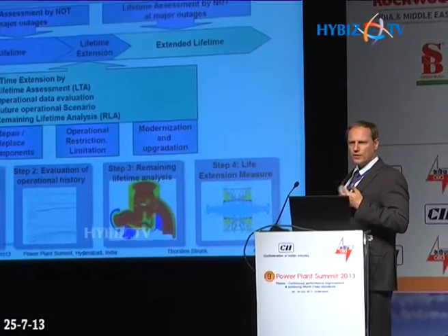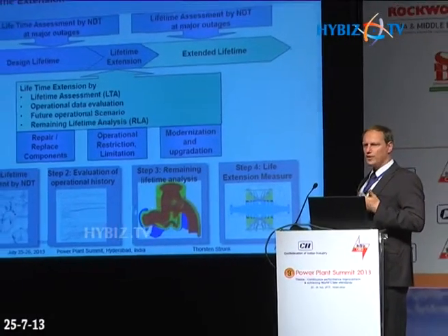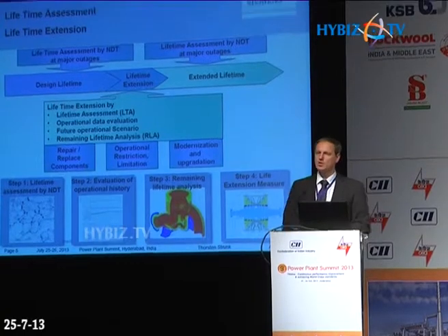And then you can do the remaining lifetime analysis, which brings you the result on which basis you can make a sound decision of what lifetime extension measures you would need to take in order to get the best bang for the buck. We used to say the most return of investment. This could mean that you say, I'm just restricting my operational mode, and maybe I just use my turbine as a peaker, or I only have reduced operation, reduced power output, or I would repair or replace components.